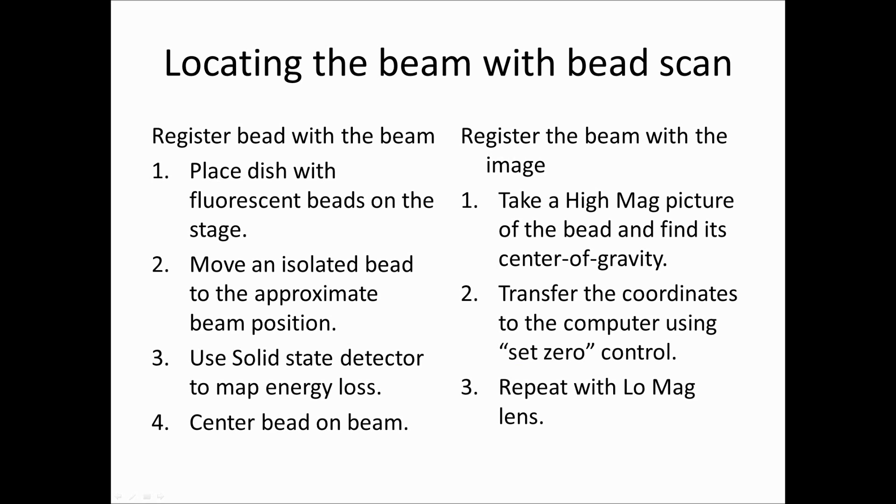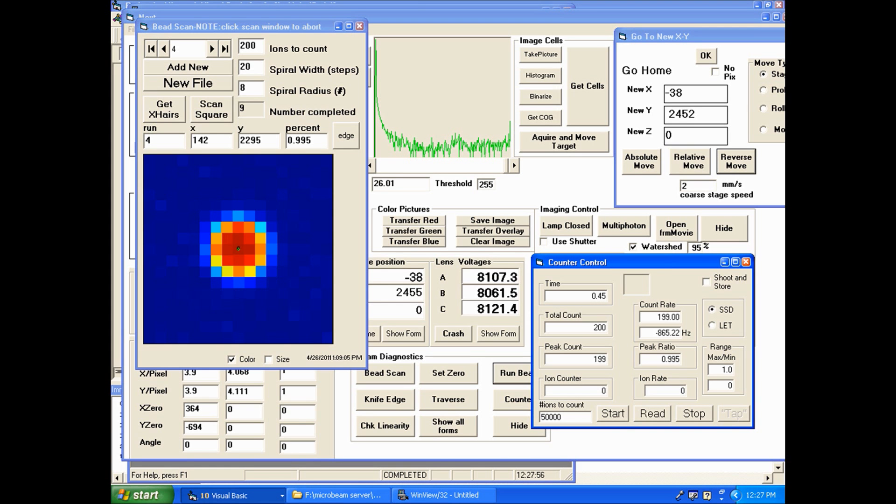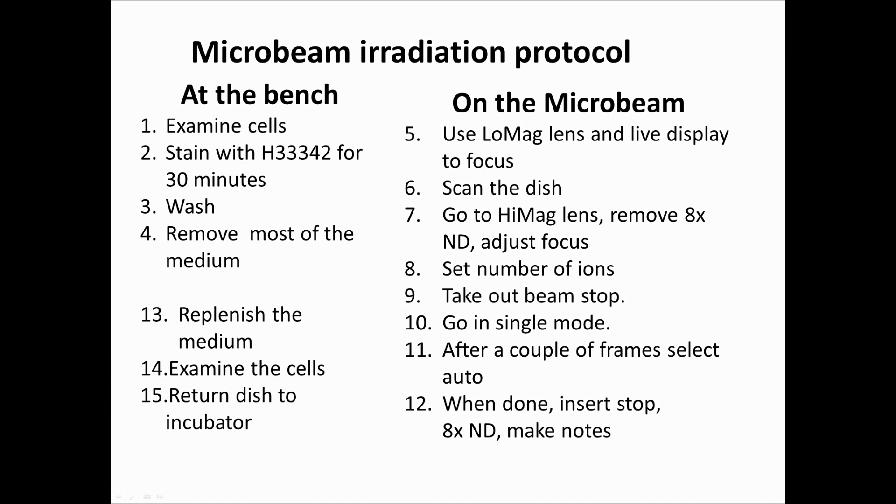So these are the steps going through the bead scan. This is in gory detail. I think you have a slightly different version of it in your books there. But we'll go through this as an exercise tomorrow. But what you get is a picture like this where the dark blue areas are where the particles are missing the bead and the red areas are where the particles are going through the bead. And either the program locates it or you can click on the center of this and that tells you where you have to move to actually center the bead on the beam axis.